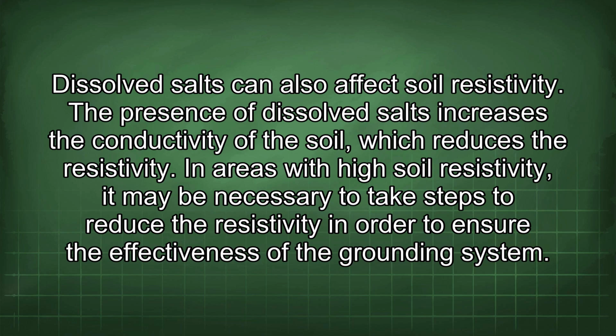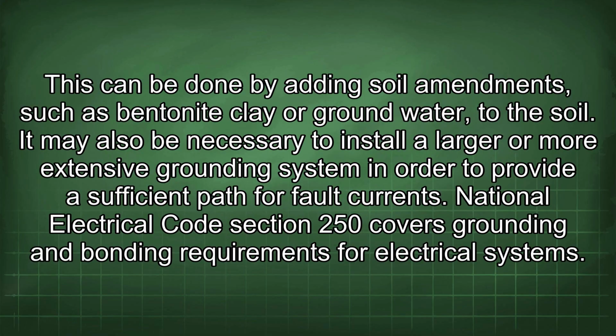In areas with high soil resistivity, it may be necessary to take steps to reduce the resistivity in order to ensure the effectiveness of the grounding system. This can be done by adding soil amendments, such as bentonite clay or groundwater, to the soil. It may also be necessary to install a larger or more extensive grounding system in order to provide a sufficient path for fault currents. National Electrical Code Section 250 covers grounding and bonding requirements for electrical systems.